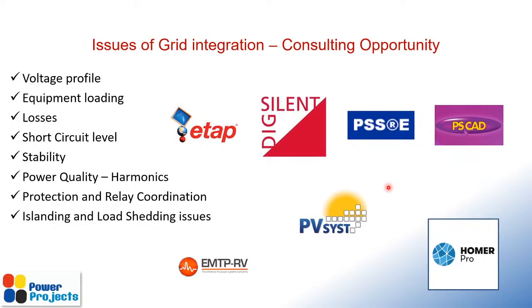In addition to LVRT and HVRT, it is really important to maintain the inertia of the system at a much better level, so that a disturbance in the system does not drive the frequency to a very low or a very high value. That's another important aspect from the stability perspective. I believe Amuda will be able to take you through this with the support of DIgSILENT PowerFactory software tomorrow, right?